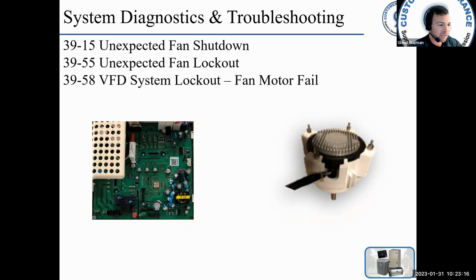3958 is originated in the VFD when the fan motor feedback is not received and the VSP value has been sent to the fan motor for 30 seconds. So basically what it's telling you there is it's telling the motor to run, and it thinks the motor is running, but it's not getting a feedback.